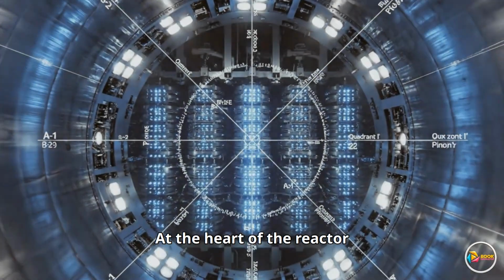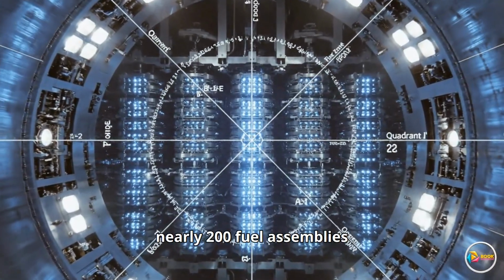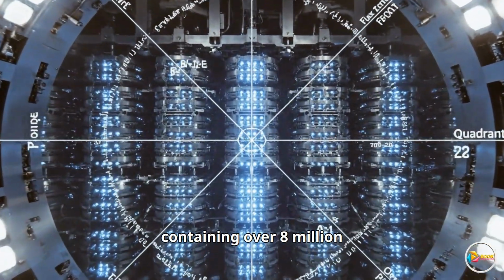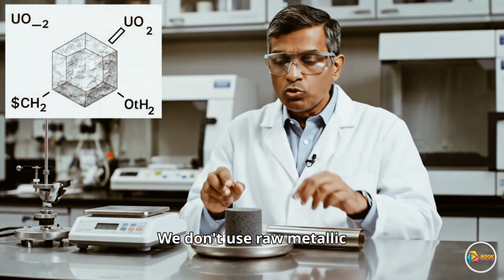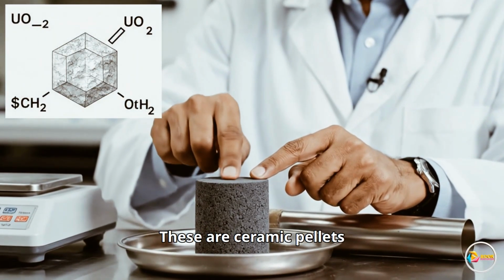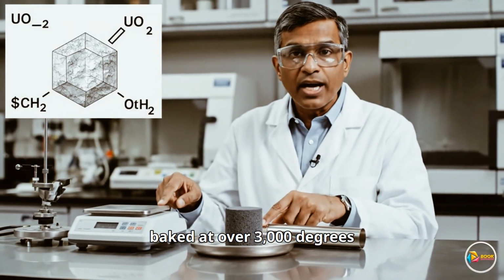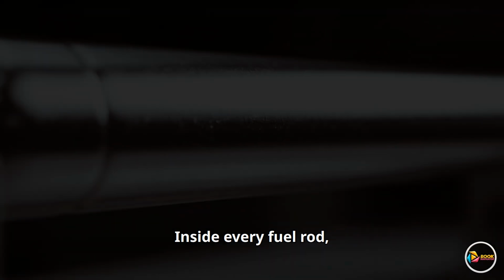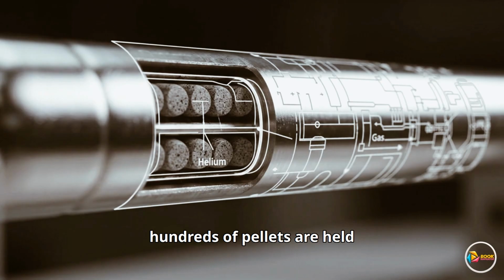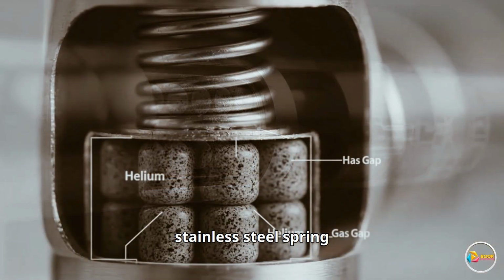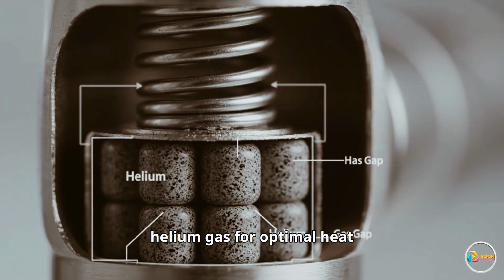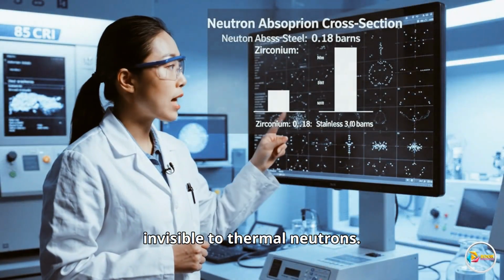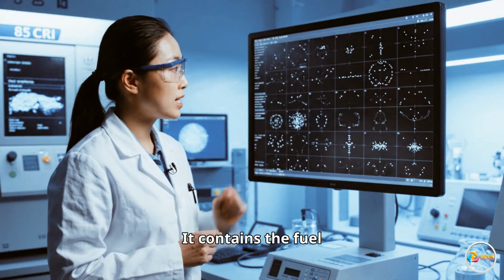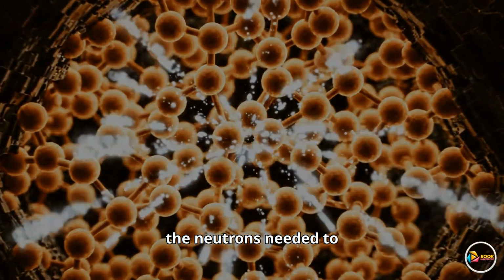At the heart of the reactor vessel sits the active core, nearly 200 fuel assemblies containing over 8 million individual fuel pellets. We don't use raw metallic uranium. These are ceramic pellets baked at over 3,000 degrees Fahrenheit. Inside every fuel rod, hundreds of pellets are held tightly in place by a stainless steel spring and surrounded by pressurized helium gas for optimal heat transfer. Zirconium is practically invisible to thermal neutrons. It contains the fuel physically without absorbing the neutrons needed.